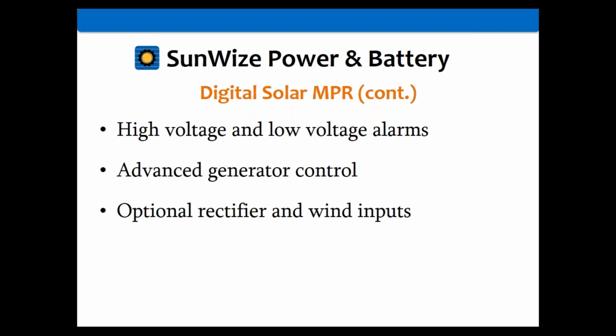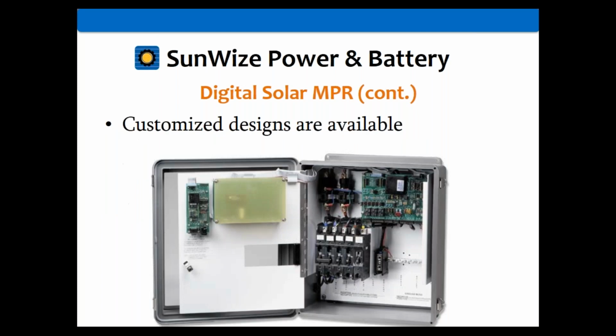It has standard high and low voltage alarms and advanced generator control built in. By advanced, I mean it can also do control based upon current as well as voltage. Kind of a neat thing for battery charging, because it has shunts in it that can measure wind and rectifier currents as well. You can run those through it, pick up the shunt and capture that information, and based upon that you can do some generator control. Some neat things you can do with it.